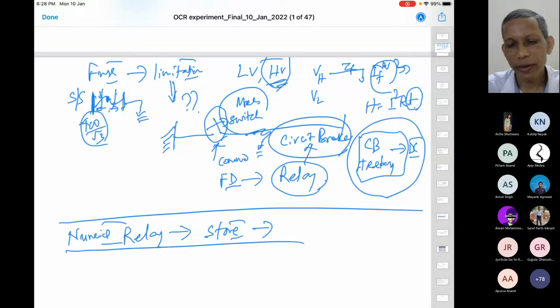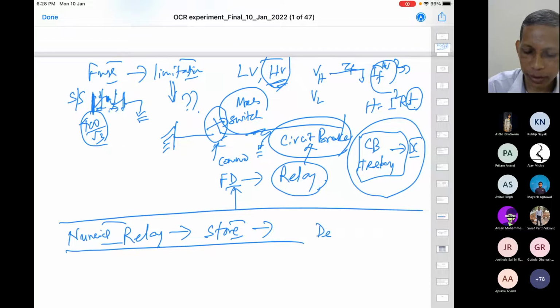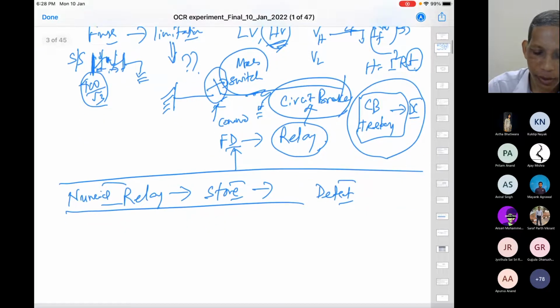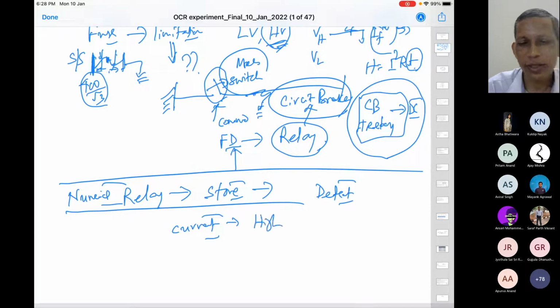So these numerical relays are being widely used now, and our focus will be on verification of different numerical relays. But as you notice here, this relay is nothing but a fault detector. So how will it detect a fault? That methodology is different for different relays, and therefore we have different kinds of relays. As you know, for any fault the current becomes high. So we say that overcurrent is a good principle to notice a fault. Overcurrent is a good indicator of a fault situation.